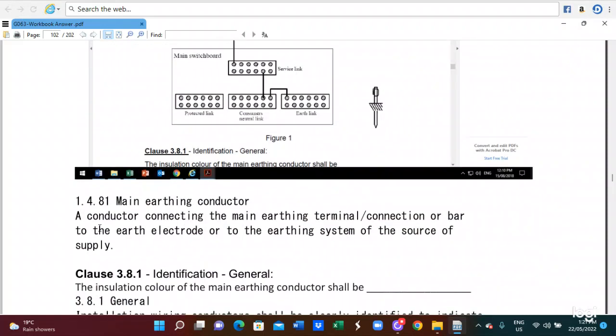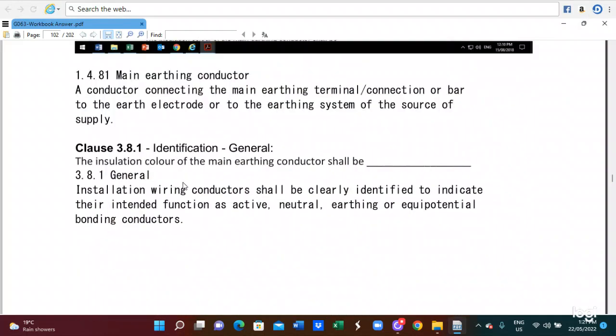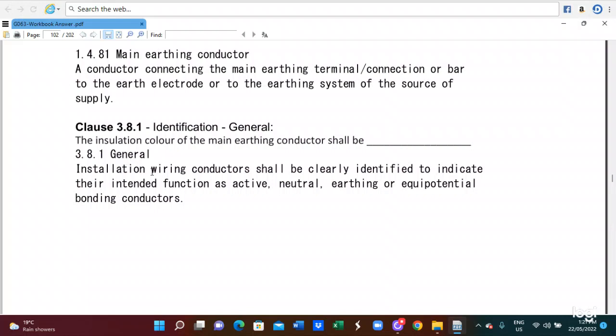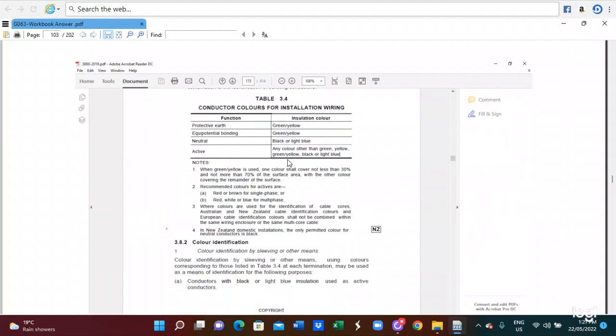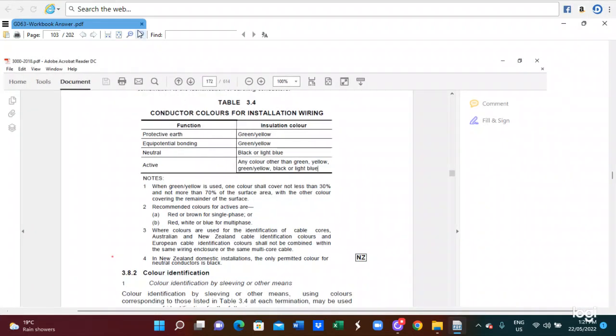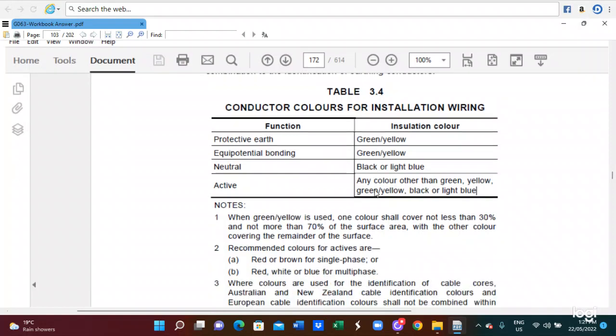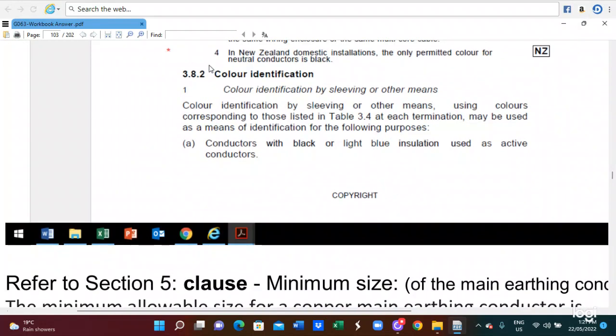The definition of main earthing conductor is expressed in 1.4.81. The conductor connecting the main earthing terminal or connection bar to the earth electrode or to the earthing system or the source of supply. So this is the main earthing conductor. For identification, you have to refer to 3.8.1. So the installation of the earthing conductor shall be clearly identified to indicate its identified function as active, neutral, earthing or the equipotential bonding conductor. In this case, you have to refer to Table 3.4 of the AS/NZS 3000. So we have to refer to the protective conductor and also the insulation color you can see in Table 3.4. For color identification, you can see 3.8.2.